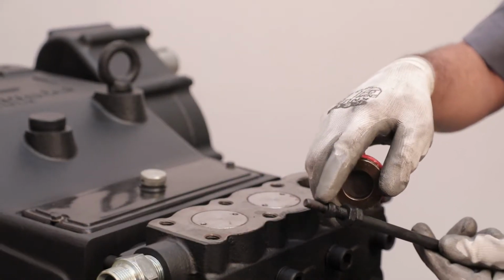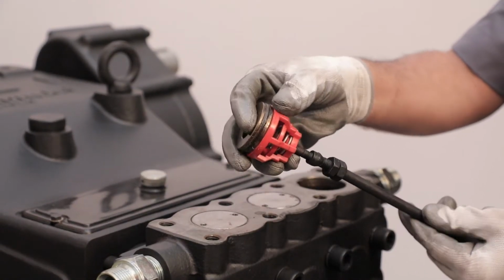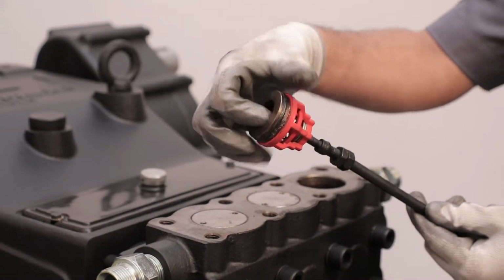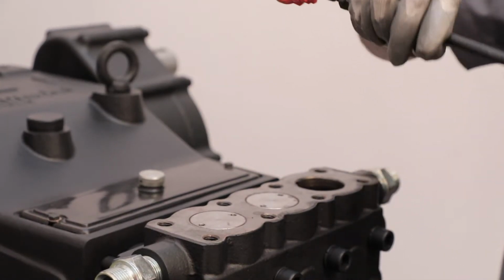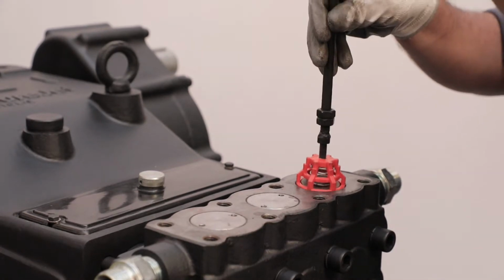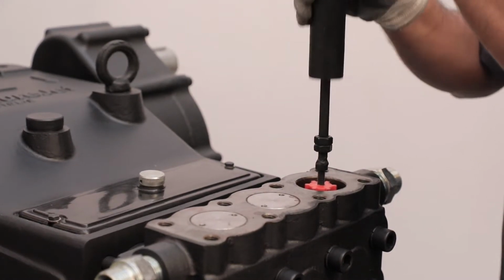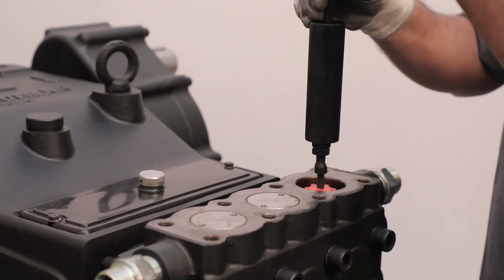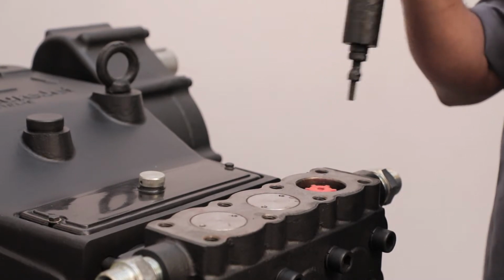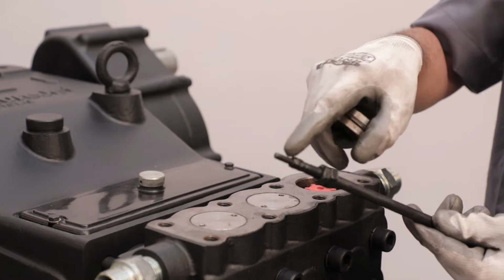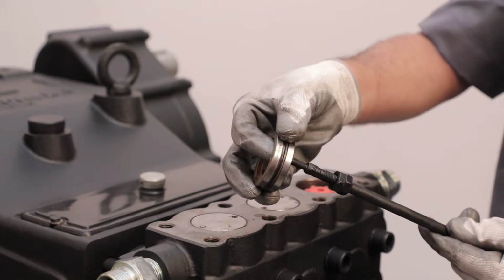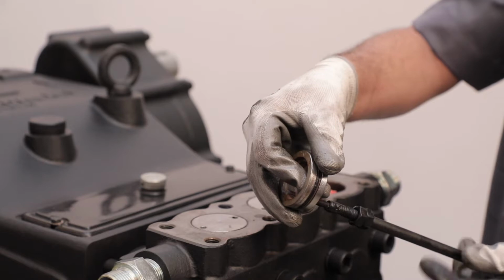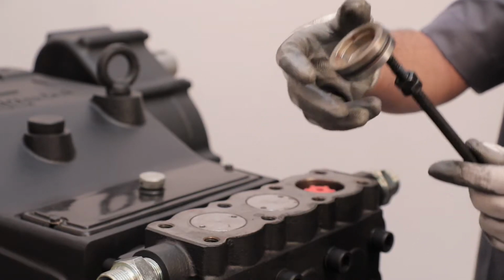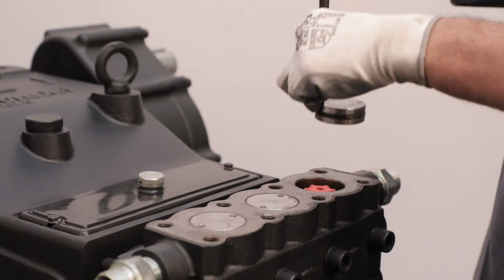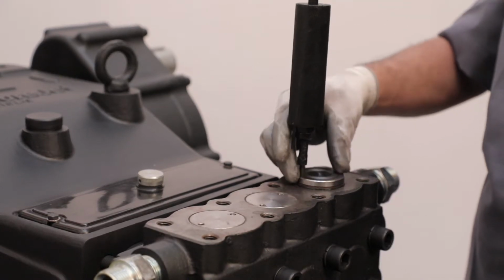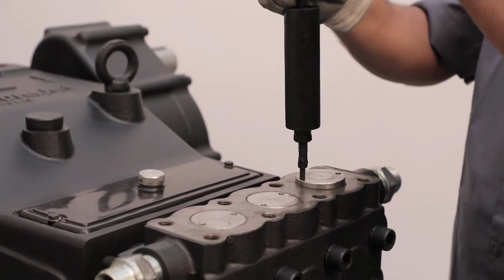Now, screw threads of valve puller into suction and discharge valve guide. Place and push valve assembly into pump head with the help of valve puller. Again, screw valve puller on discharge valve holder and put it in its proper place into the pump head and push valve holder using weight of valve puller.